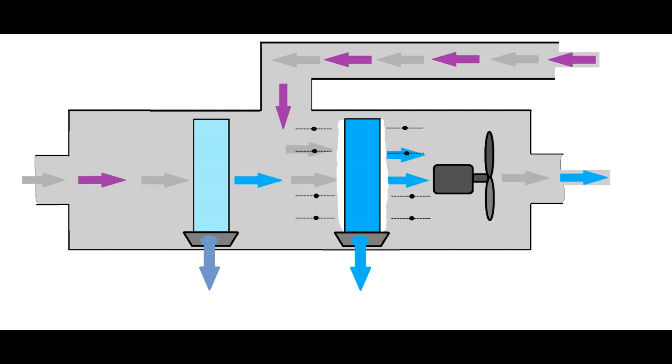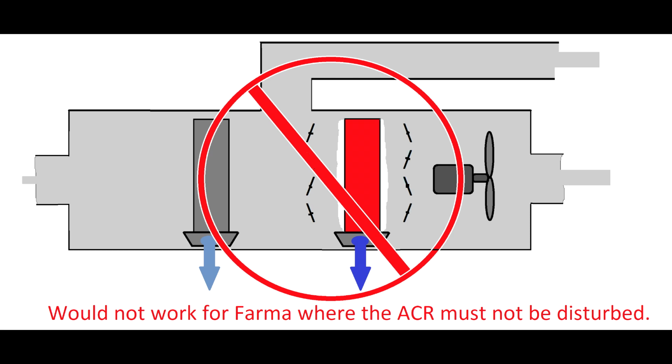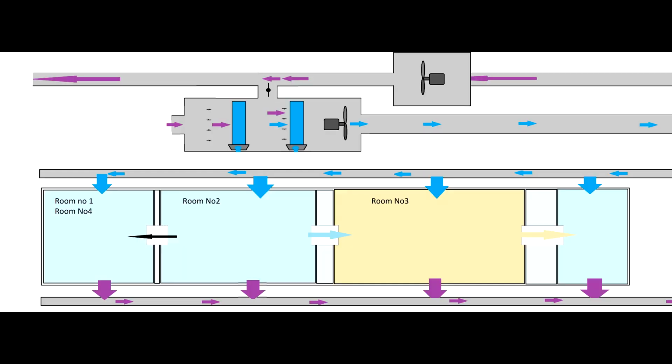This is a dangerous situation because in pharmaceutical industry we have to take care of the air change rates and pressure cascade. But technicians are smart. They said, well, I'm going to put a damper and I will close the damper and I will put the heat exchanger on defrost. I will melt the ice and then it will restart its cycle again. This thing doesn't work for pharmaceutical industry because once you restrict the airflow, you lose the air change rates and the pressure cascades, and that will lead to a disaster where you might lose the entire product you just built.